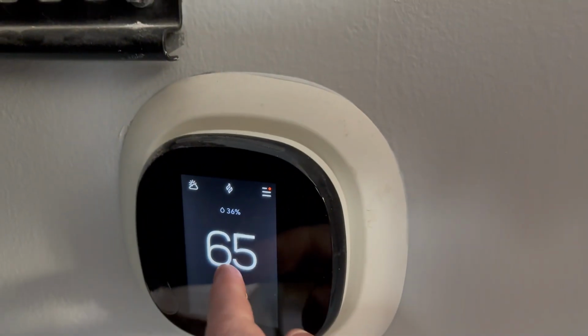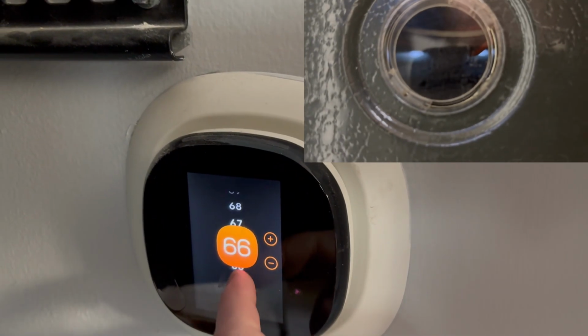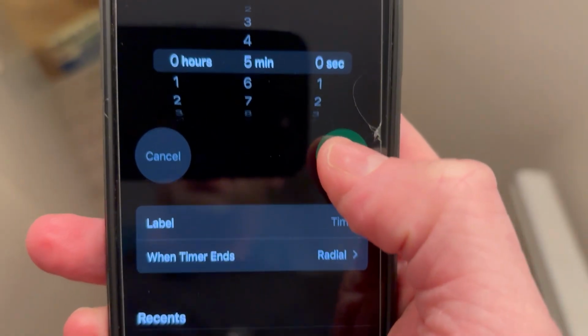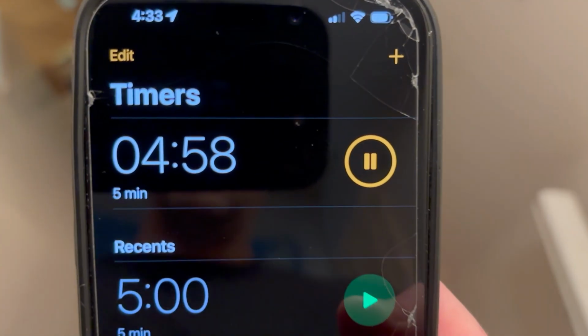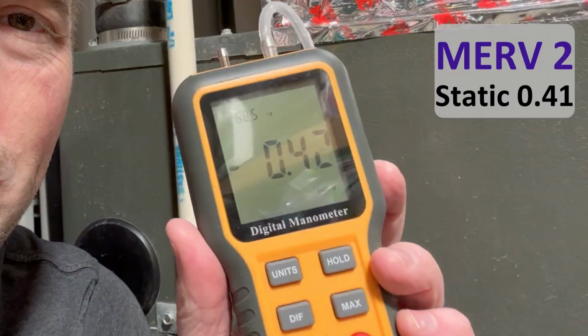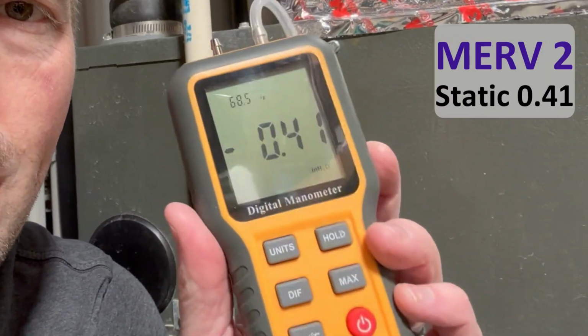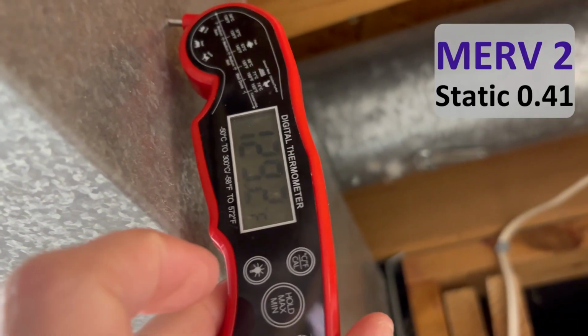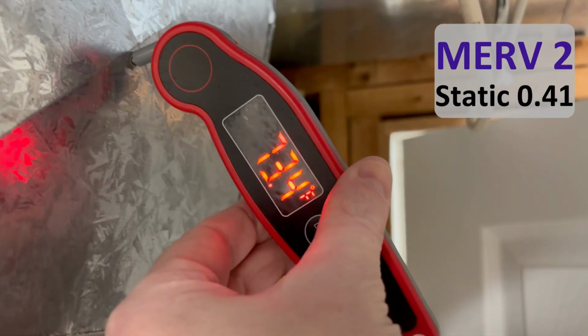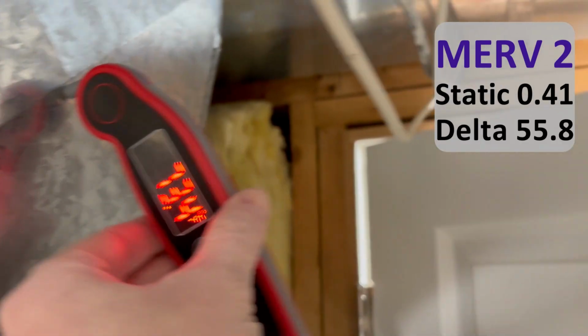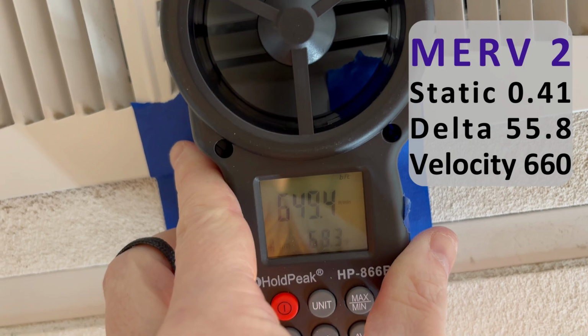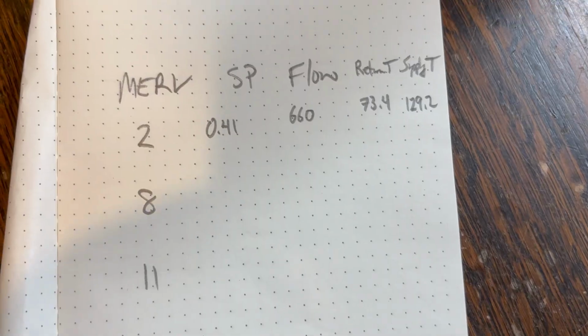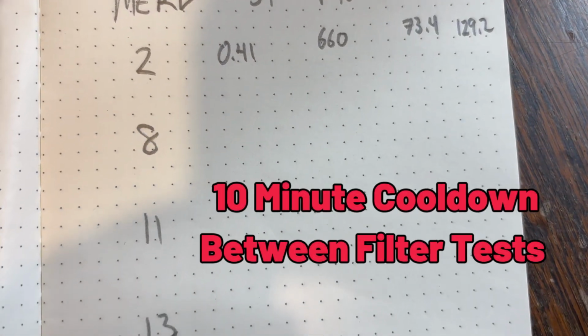For the testing, I want to make sure the burners are on, so I'm bumping the thermostat up to 70 degrees to ensure we're heating throughout the entirety of our testing. For each filter, I'll let the furnace run for 5 minutes before I take measurements. All right, we just hit 5 minutes. Going to take our readings. Static pressure, 0.40, 0.41 for our MERV 2. Supply temperature, 129.2. Return temperature, 73.4. Airflow of about, let's call it 660. We'll split the difference. I'll log my readings in our handy dandy notebook, and then I'm going to just repeat the process for the rest of the filters.